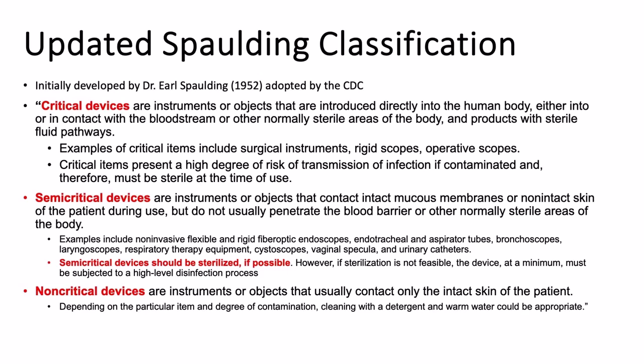Semi-critical devices are instruments or objects that contact intact mucous membranes or non-intact skin of the patient during use, but do not usually penetrate the blood barrier or other normally sterile areas of the body. This would include flexible and rigid fiber optic endoscopes, endotracheal and aspirator tubes, bronchoscopes, laryngoscopes, respiratory therapy equipment, cystoscopes, vaginal specula, and urinary catheters. Semi-critical devices should be sterilized if possible. However, if sterilization is not feasible, the device at a minimum must be subjected to high-level disinfection.